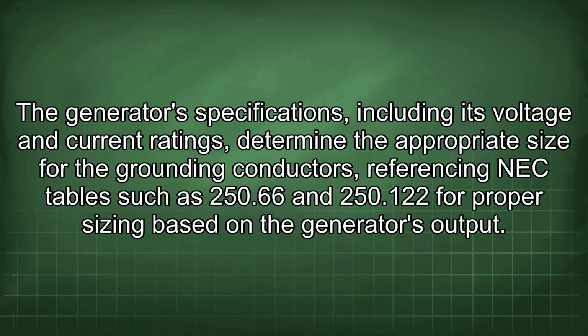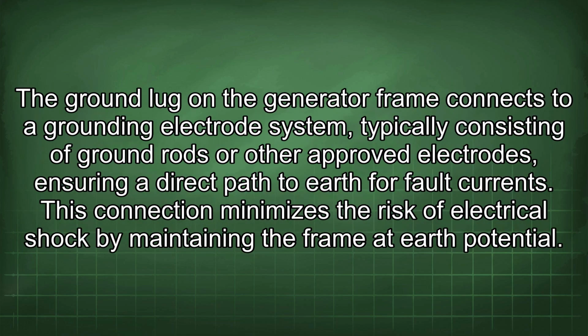The generator specifications, including its voltage and current ratings, determine the appropriate size for the grounding conductors, referencing NEC tables such as 250.66 and 250.122 for proper sizing based on the generator's output. The ground lug on the generator frame connects to a grounding electrode system, typically consisting of ground rods or other approved electrodes, ensuring a direct path to earth for fault currents. This connection minimizes the risk of electrical shock by maintaining the frame at earth potential.